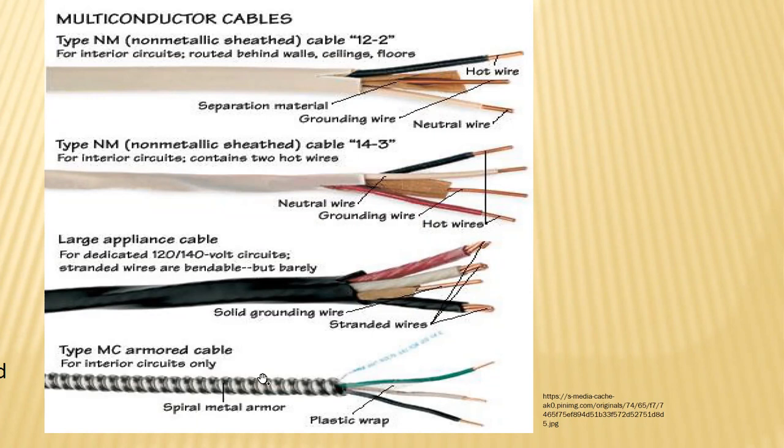Now, when it comes to installations, non-metallic and metallic, the non-metallic, you can't install on metallic framing, or steel framing. You're going to notice that some of the buildings will be built with a timber framing, which is a wood framing, and some of the households or buildings will involve steel framing. If it's a timber framing, you can surface mount on the framing. You can mount either this or that directly onto it. If it's a steel framing, you can't mount non-metallic.